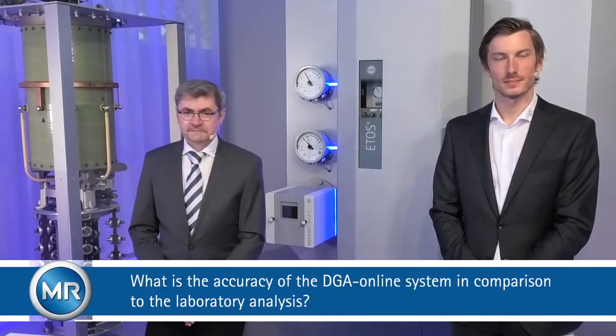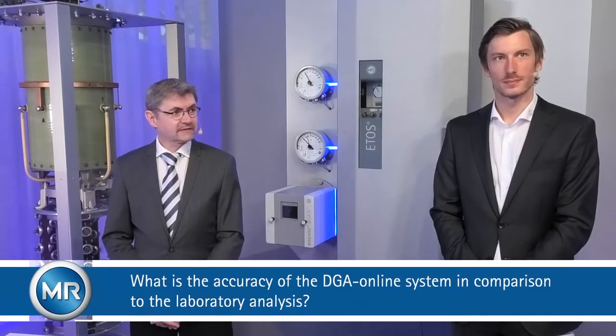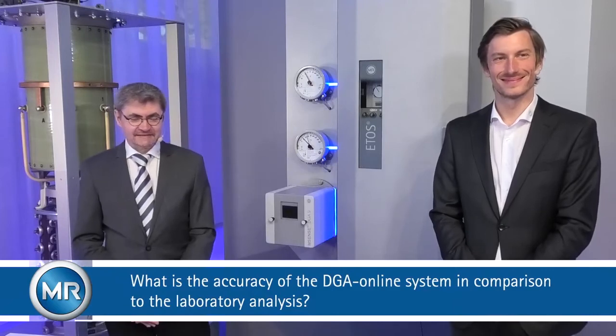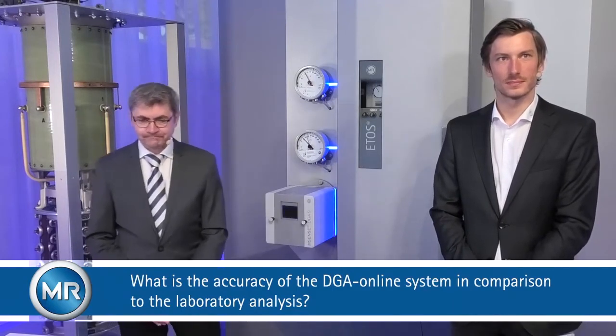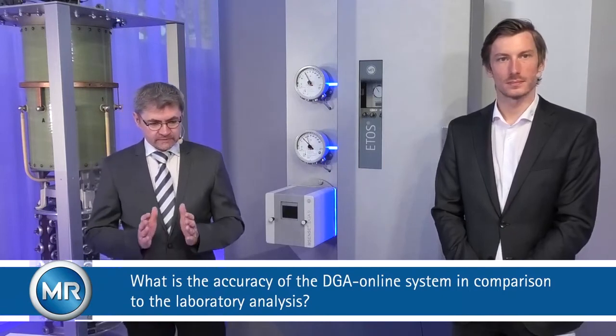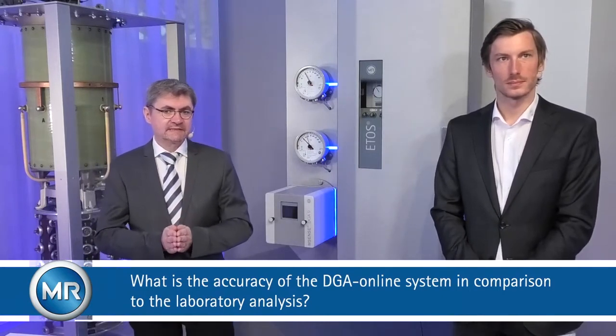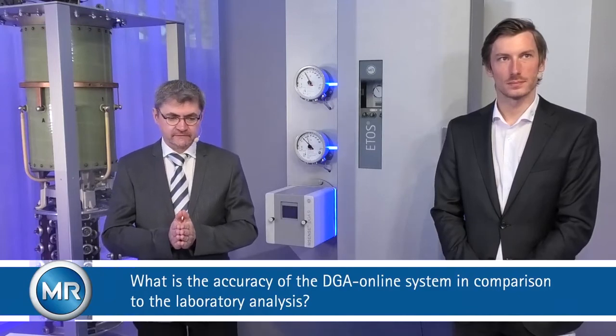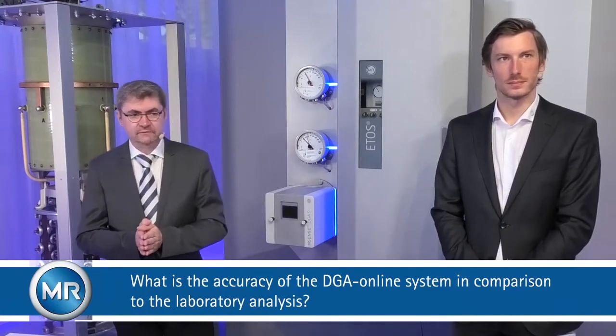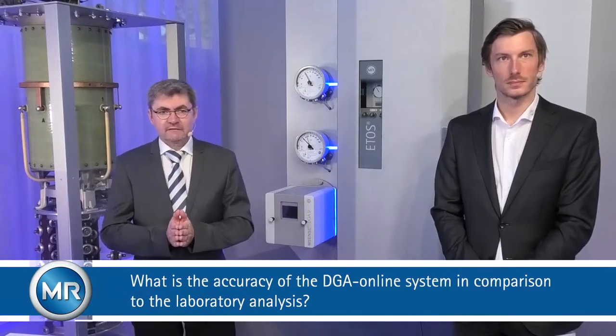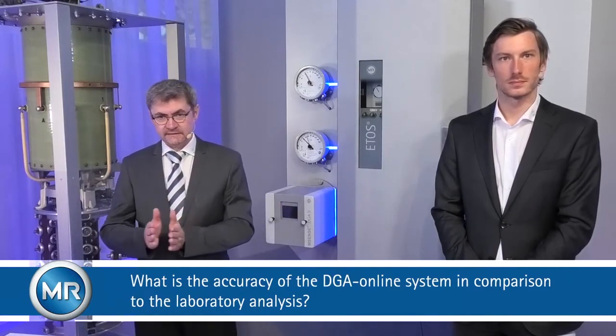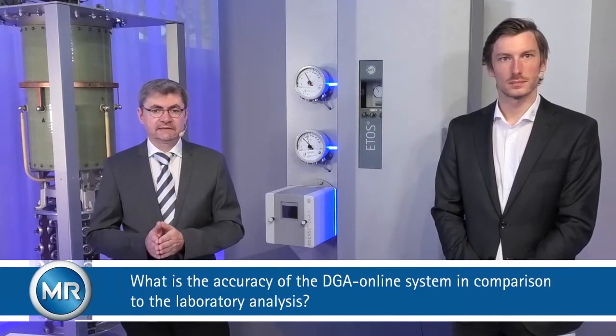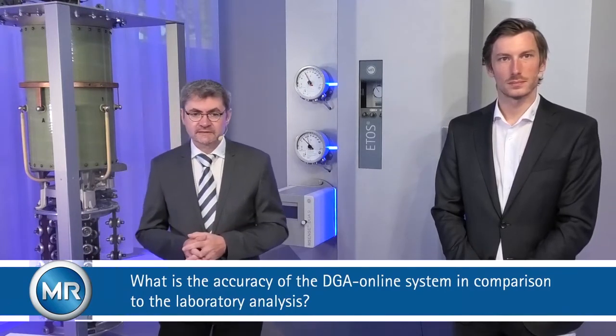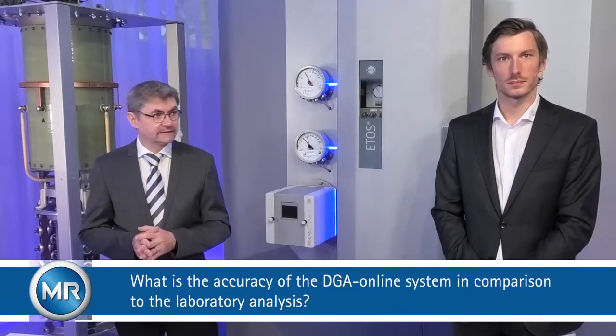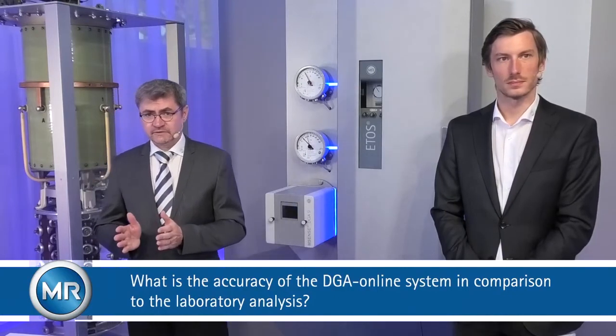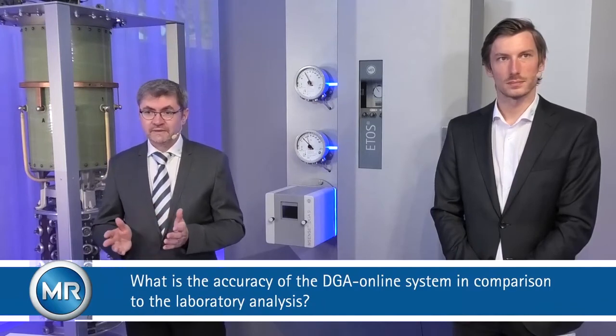Also an easy question, but not that easy to answer: the discussion about accuracies. When we start looking at measurement uncertainties from a laboratory analysis, for example, and compare laboratory analyses between different laboratories, as was shown in the last round robins done with over 15 laboratories in recent years, you can get differences and uncertainties up to 25%.